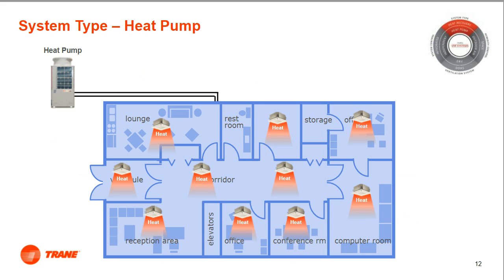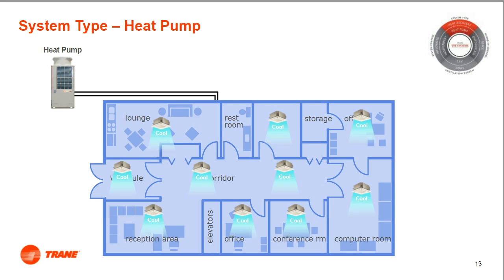VRF heat pump systems are a heating and cooling changeover system. This means they can only operate in one mode or the other. When in heating mode, all zones have heating available to them. No zones can cool. When in cooling mode, all zones have the cooling available to them. No zones can heat. So, it has a heating mode and a cooling mode. Of course, the transition between modes is not instantaneous. During those transitions, the system neither heats nor cools.